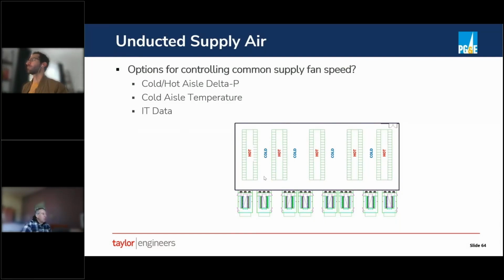And that will ensure that you have cold air all the way down your aisle, and that the servers aren't sucking backwards through cracks or through empty spaces in the containment. If there are cracks or gaps in the containment, and there always are, this positively pressurized air in the cold aisle will just push through those gaps into the hot aisle. So that's the most common way.